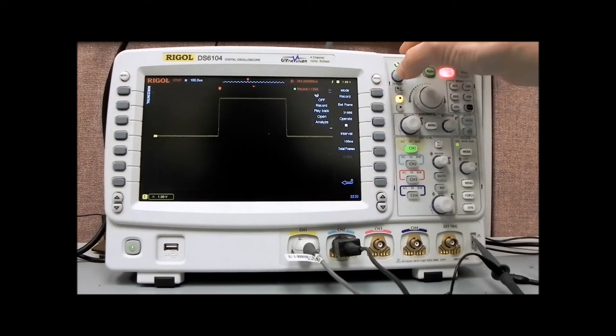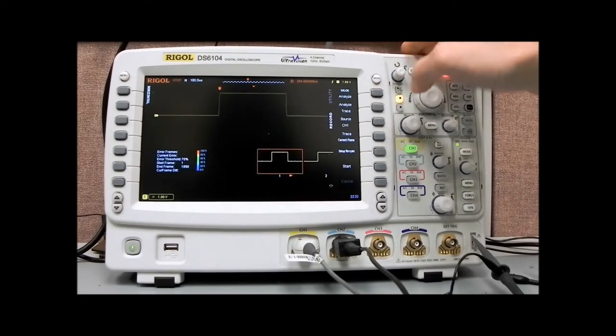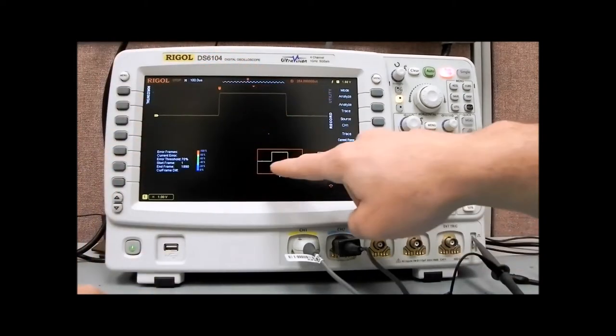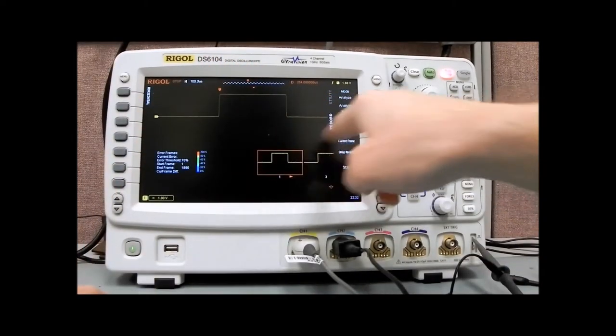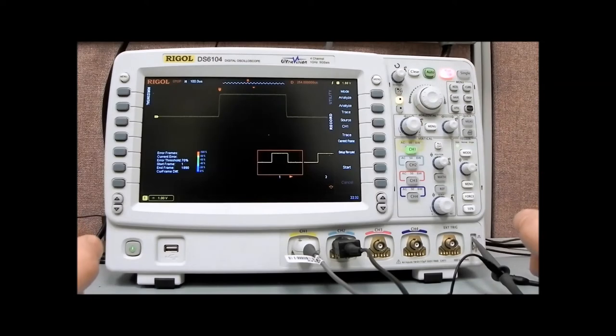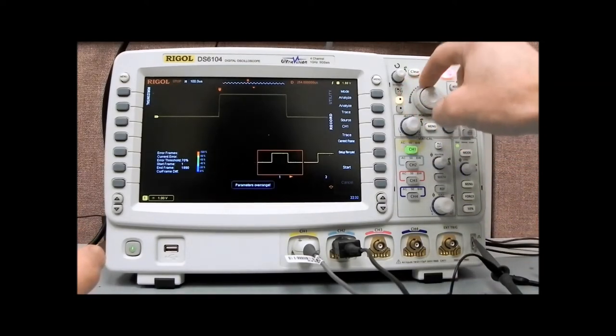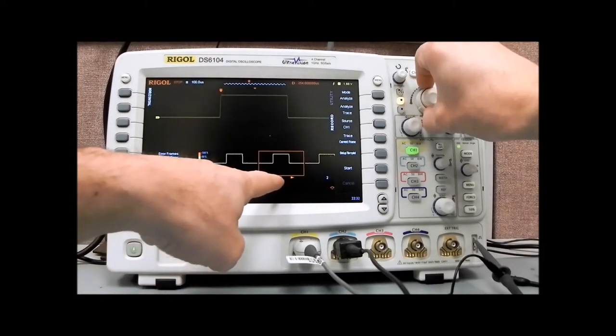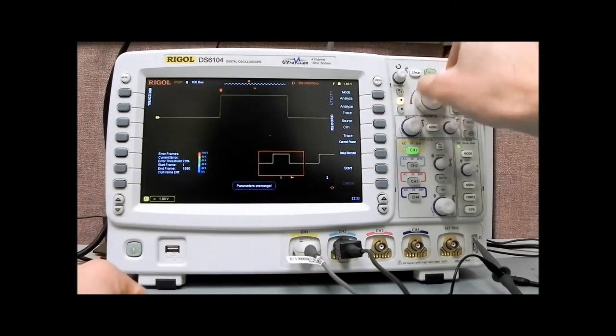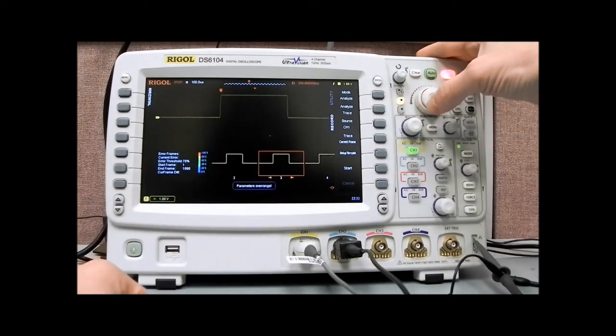Now let's go to analyze. In analysis you'll see now we have a split screen. On the top screen we have a picture of the first frame of the waveform. We can select any number of those by using either the outer ultra-vision knob, which gives us a fast-forward effect. You can see we're zipping along, we're at 1890 frames. Or we can do one at a time using the inner knob, where we go 5, 6, 7, 8, and back again.